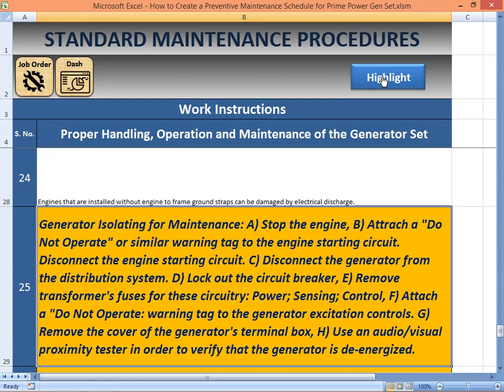Remove the cover of the generator terminals box. Use an audio-visual proximity tester. You have to test in order to verify that the generator is de-energized. Remember, this is 400 volts or 480 volts. The amperes is very high. And this is three-phase. So very dangerous for electrocution or electric shock, okay? Or arc flash, arc blast, okay? So this is for your own safety, okay?